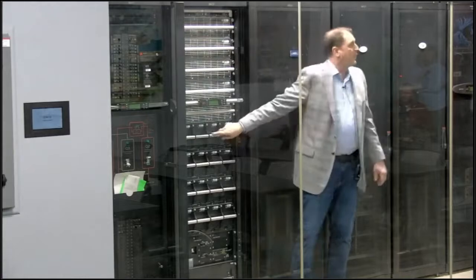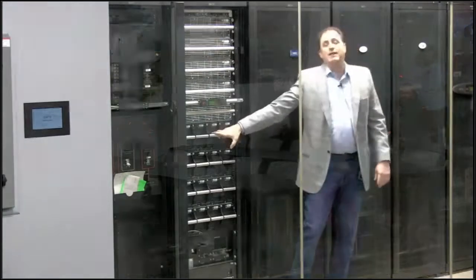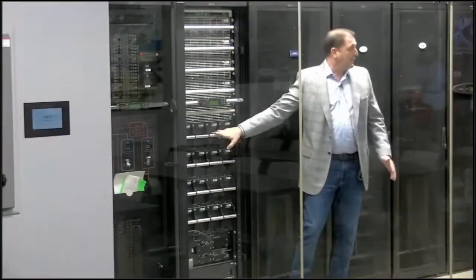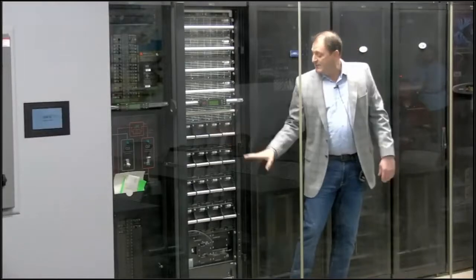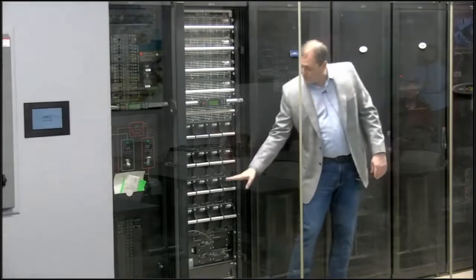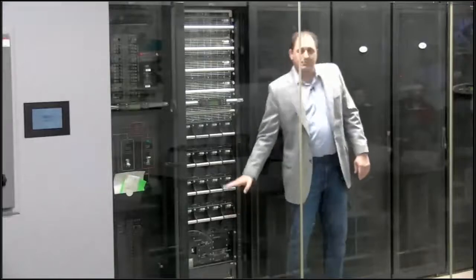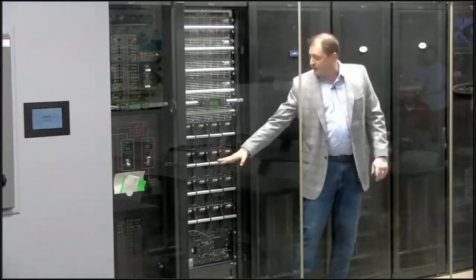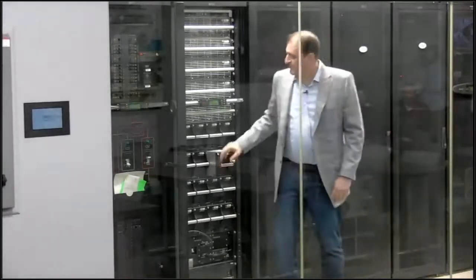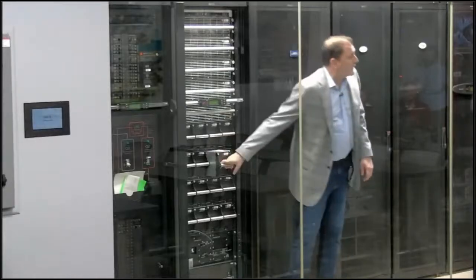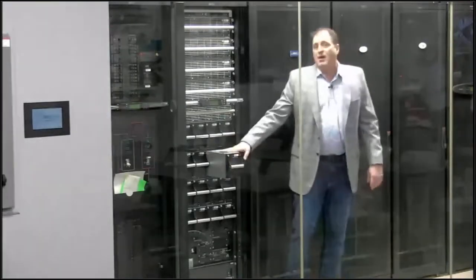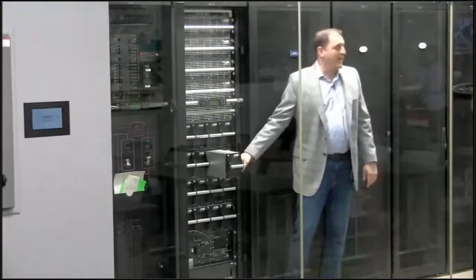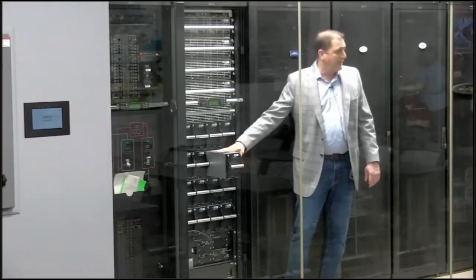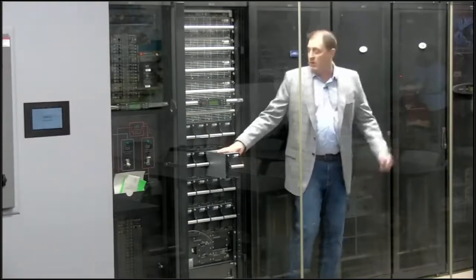Additionally, Scott talked about batteries, and batteries being the way that power is delivered inside or from a UPS. I have 1, 2, 3, 4 shelves or separate strings of batteries available. And if I take a battery out, all I have done is taken that string of batteries, that shelf, offline. And I can do this once again while the UPS is hot.